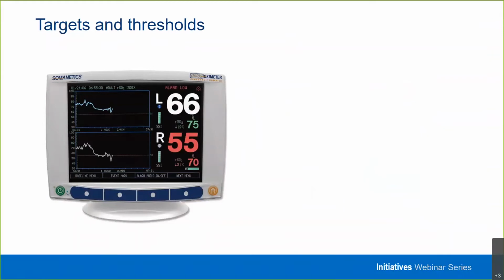Brief information about targets and thresholds and how to use the device. We know from evidence that I'll show you in just another couple of slides that normal values run between 60 and 80 in healthy patients. The device displays information bilaterally. There's a sensor on each hemisphere of the brain, left and here on the right. It gives you trend information over time.